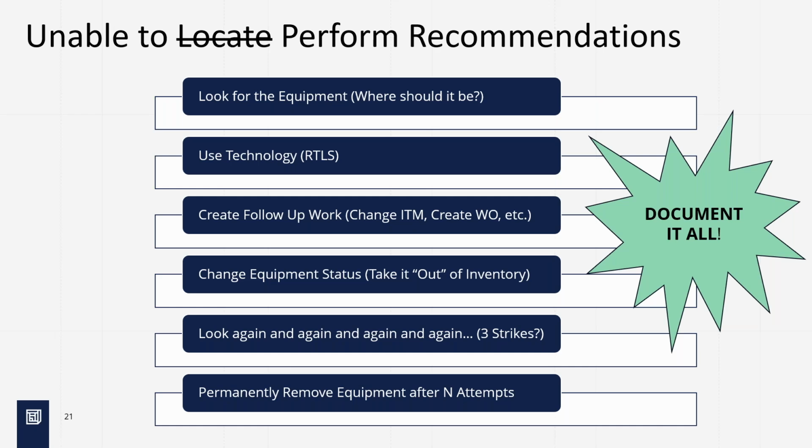But the work order is closed on the UTL status. And then from a completion reporting standpoint, that gets filtered out, I would imagine? Yeah. It's flagged as incomplete, unable to locate, and generates a new PM work order as a UTL. Okay. I like that. That's a cool approach.